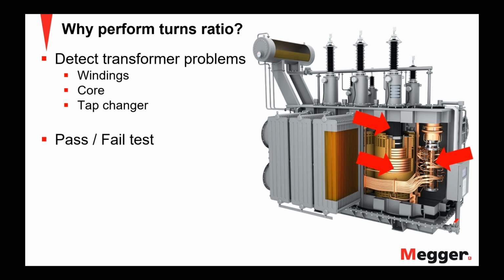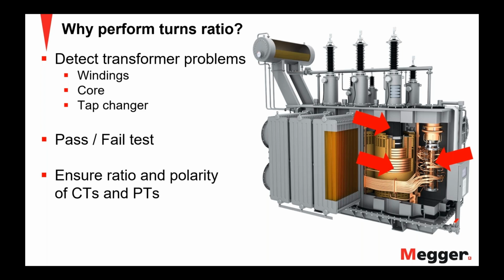And turns ratio is typically referred to as a pass-fail test. If turns ratio fails, then the fundamental electromechanical parts inside the transformer likely have an issue, and any other testing that you would do would not be worthless, but would just further confirm that this transformer has significant problems. So that is why turns ratio is typically the first test that's done on a transformer before doing anything else, because you want to understand, is the core and the windings doing their job and being able to transform that voltage as is required. And it can also be used to ensure the ratio and polarity of instrument transformers like CTs and PTs.